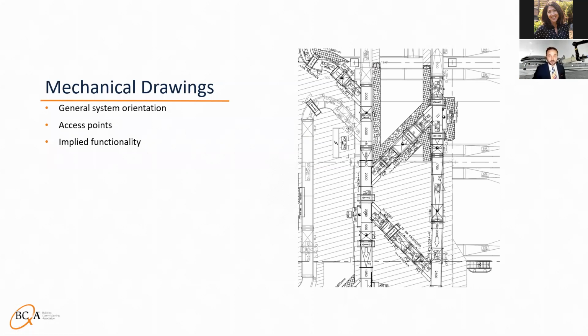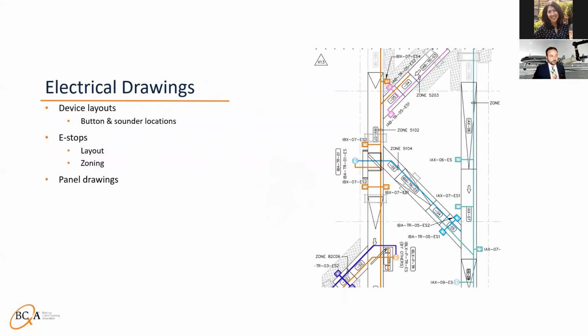Next, once mechanical drawings have proceeded to a pretty stable state, electrical drawings will start to be produced. There's drawings for device layouts that show where buttons and other panels are in the field, and also e-stop layouts showing where e-stop buttons and lanyards will be and which conveyors are controlled by them. The rules on how to do this will vary both by culture at the airport and by local codes and other requirements. In many places, you do not stop the whole thing from one e-stop because it's a very wide-ranging system. And if a guy at a pier e-stops because he wants to go for a coffee break, you don't want to shut down the entire place. In many cases, e-stops will stop the line that it's working on, so that if somebody's responding to an event and somebody's stuck in it, you'll hit the e-stop in that area to stop the system there.